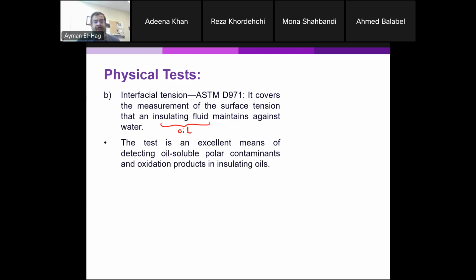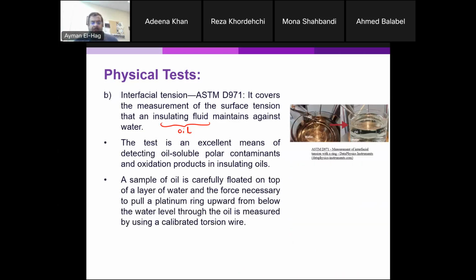So oil-soluble polar contaminants, like for example, water. It's a good way to detect water in the transformer oil, or if there's any oxidation, any chemical reactions with oxygen. So that will lead to some oxidation of the oil. It's also a very good way to measure that. So basically what you have here, you have a sample.